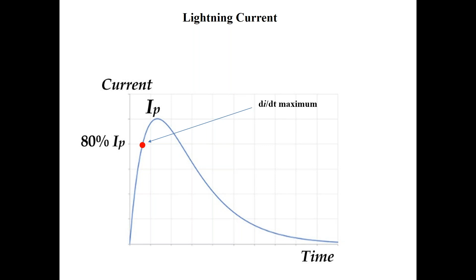One important thing about this lightning waveform is that typically, when the lightning current is around 80% of the peak value, we reach the maximum di by dt - the rate of change of current with respect to time. In the next slide, you will find that when we calculate the voltage due to the lightning current, di by dt plays a very important and significant role. So the 80% IP is usually the time at which we get the maximum voltage.